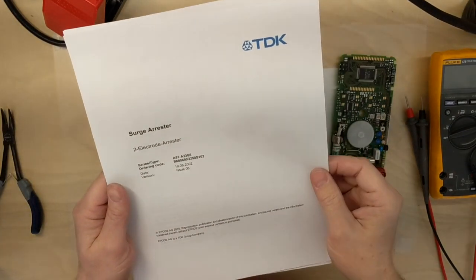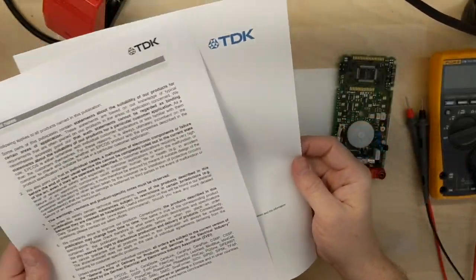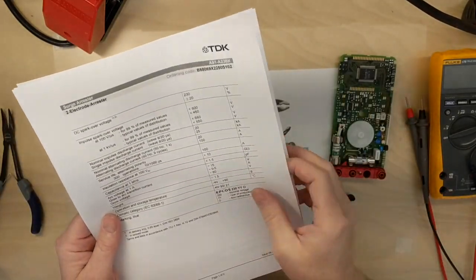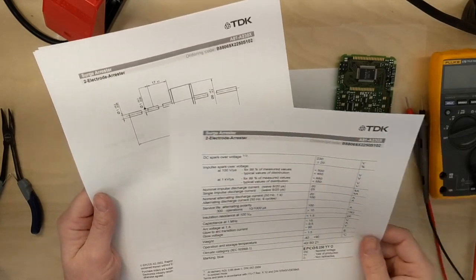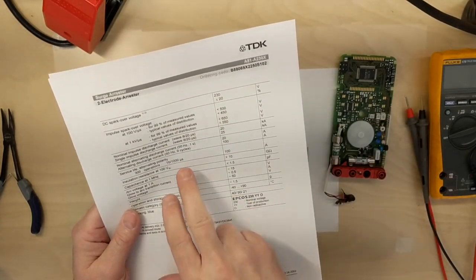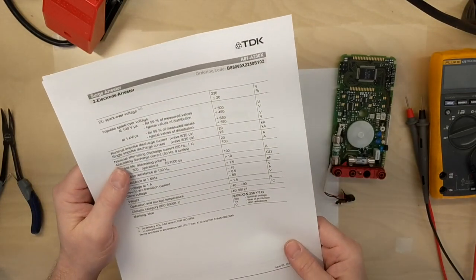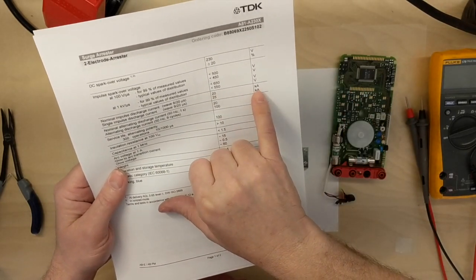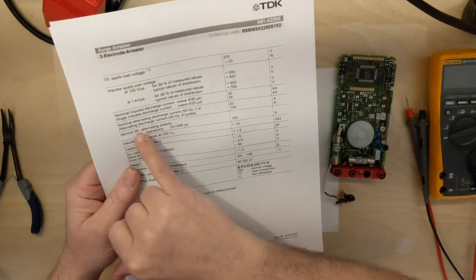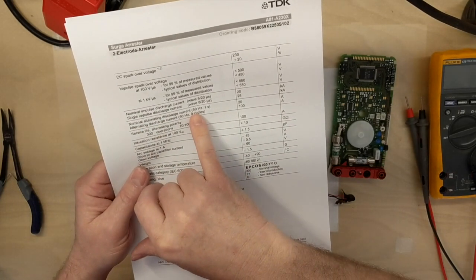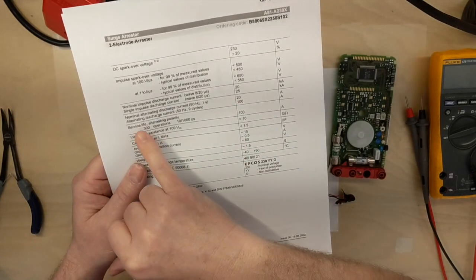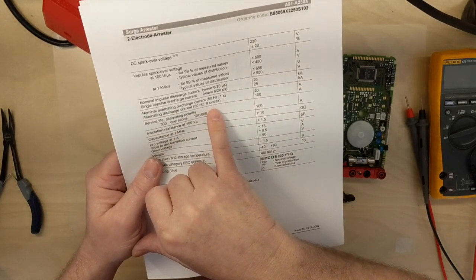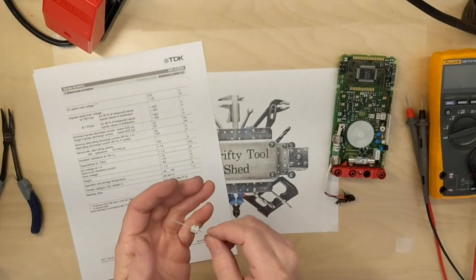I do have a data sheet here and some information on a similar device. This is a TDK on a similar device, not the exact specs of this one, but we can look at how it's got the 230 volt spark over voltage. Nominal impulse discharge current of 20 kiloamps. Actual nominal alternating current at 50 hertz for one second is 20 amps, and actually on AC discharge at 50 cycles it can actually go nine cycles at 100 amps.